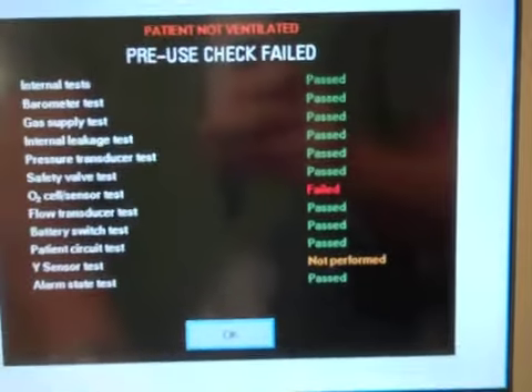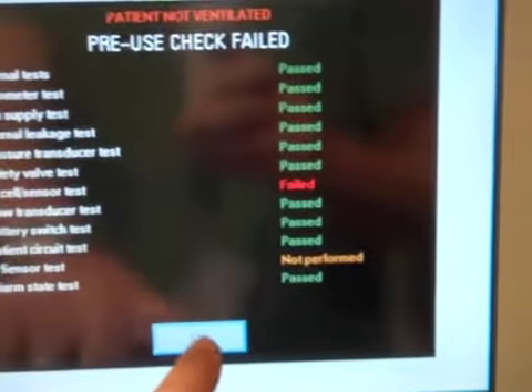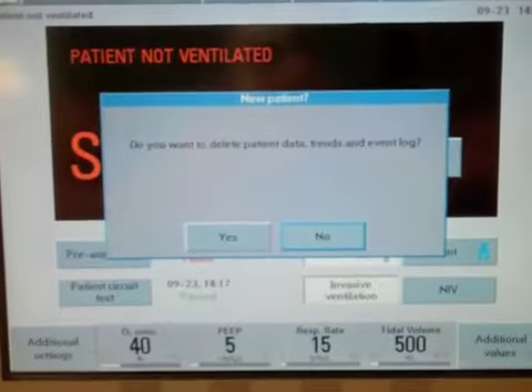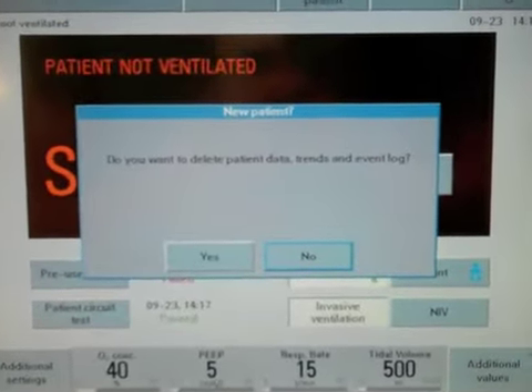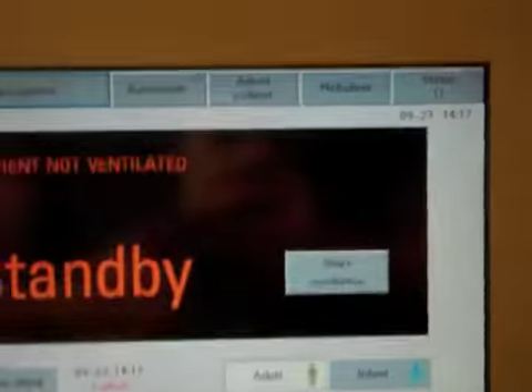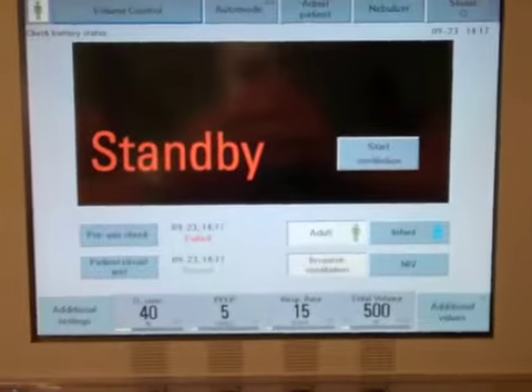So right now it's telling me that I did not perform my Y sensor test. It didn't detect that anything was plugged into that module on the side. Everything else passed except for my O2 cell, which we know the reason why. So I'm going to go ahead and start that. It's asking me if I want to delete patient trends and data. Yes, I do. Now, here's the startup screen for the Servo Y.